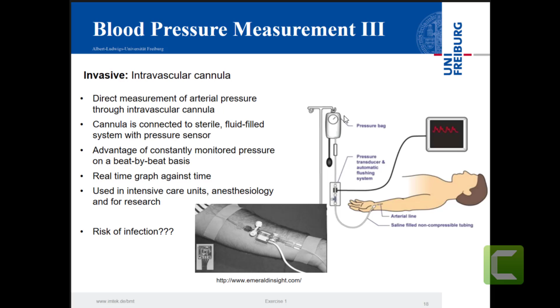You should be very careful with the height of the catheter. If the catheter is not at the height of the brachial artery, for example, then you get wrong values. After that, you also have a transducer that changes these blood pressure values into digital ones, and then you see these values on the monitor. The most important risk is infection, because you are placing something into the artery, so it can get infected. This is the typical main problem, but usually nothing should happen. And it's used in intensive care units.